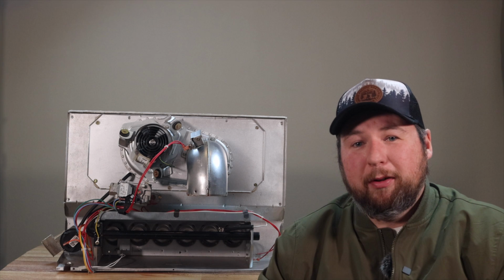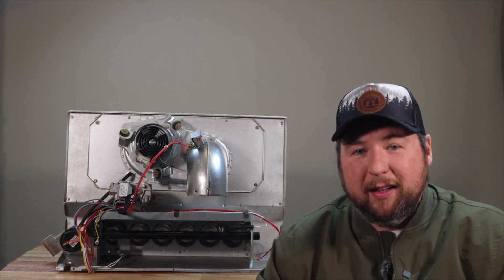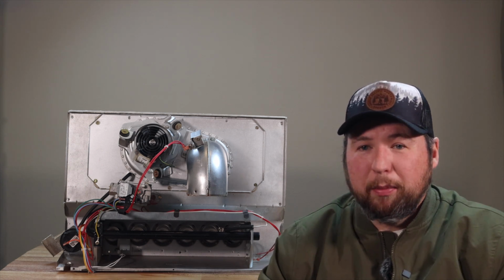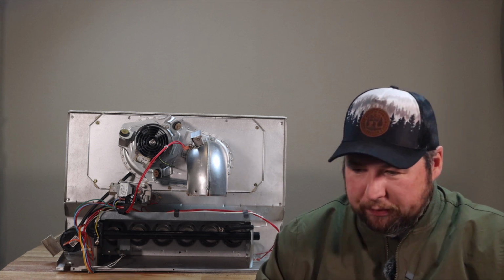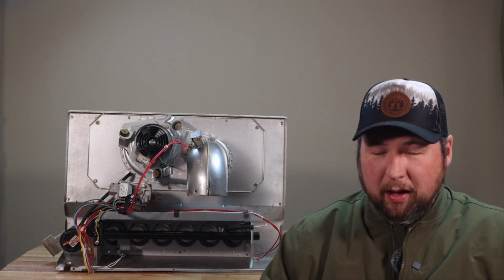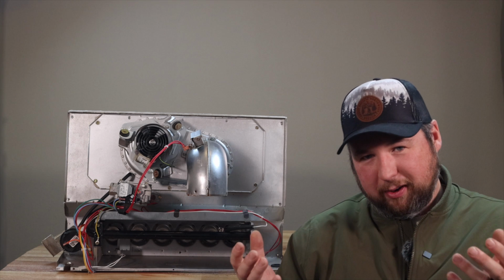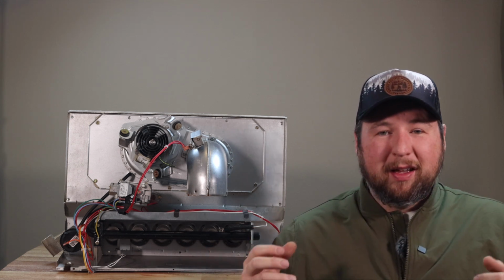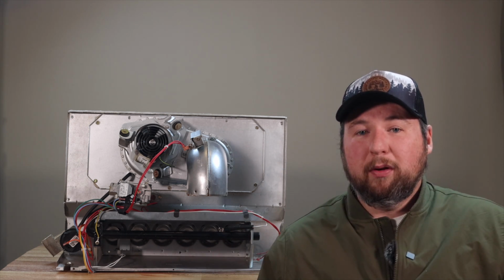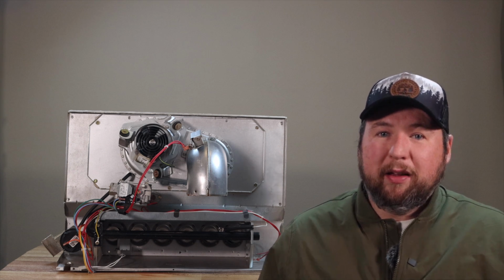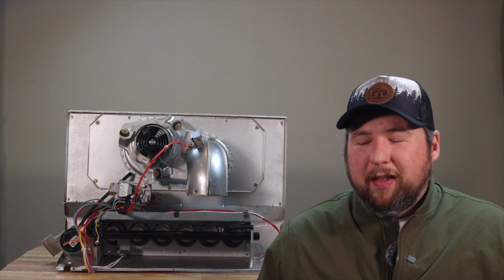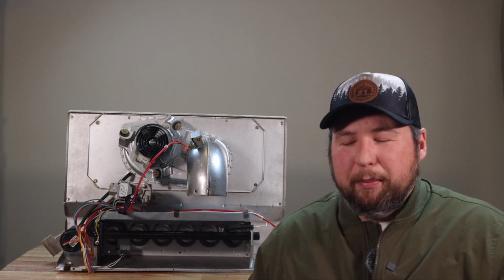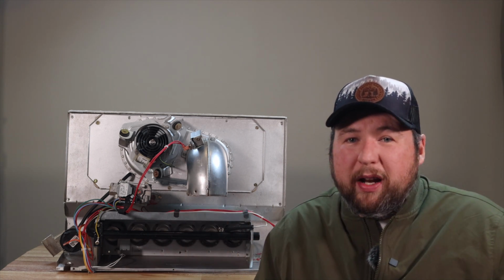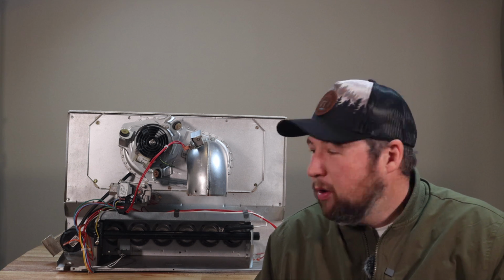And why is it 80%? Well, 80% of that heat that it produces pretty much goes in the home, 20% is going out the flue. So that's a drastic improvement. Also, if you want to consider fuel utilization, it's going to be using less fuel to produce the same amount of heat as an older furnace. So there are efficiency things, there's a lot of calculation I'm not going to get into, but basically that's a good way to understand where they go.